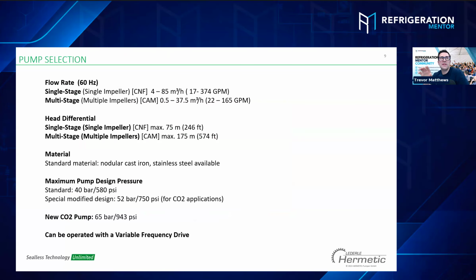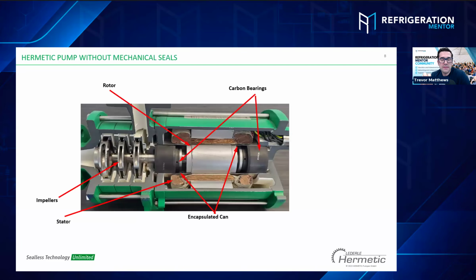Okay, so that's a quick question for me. I haven't pulled one of these pumps. If you go back to that last picture, there are times, and we'll talk about it later, when you get flash gas or cavitation. I've heard before where it could damage the impellers. And these impellers, can they be repaired or replaced? And we'll get into that later. But I just want to know, if I get one damaged, can I pull this pump apart, change those impellers, and not have to change the motor?